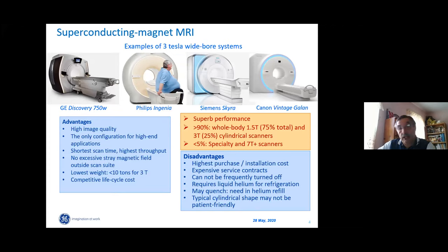Superconducting magnets for MRI: the alternatives are resistive and permanent magnets. The first systems were resistive magnets, 0.15 Tesla, introduced by a company called Fonar. It's in New York State. This company still exists and still makes resistive scanners. Advantages of superconducting scanners are high image quality, because we can achieve a significantly higher field, a factor of three higher. It's the only configuration where we can really see the tiniest points in the human body. The resolution is no less than 2 millimeters.